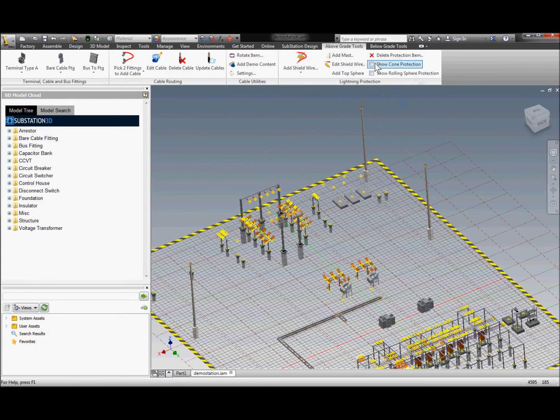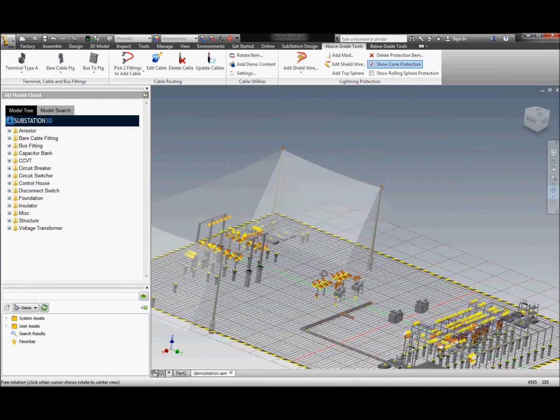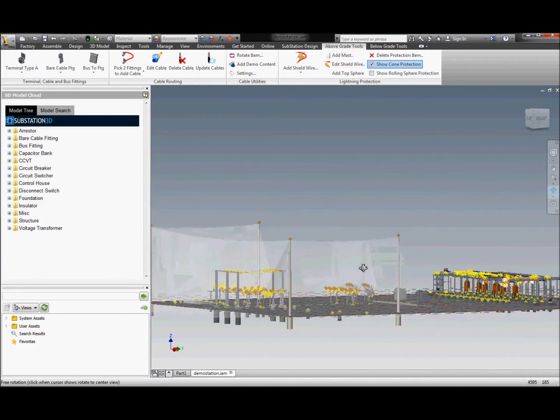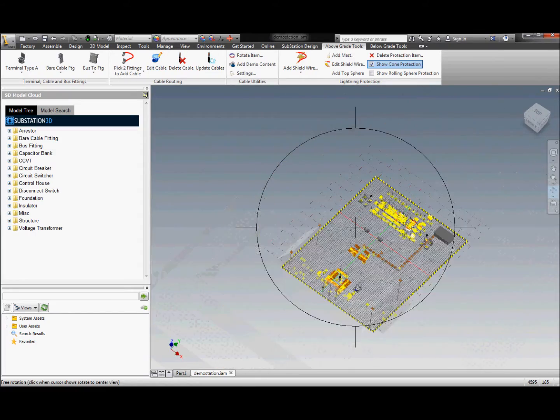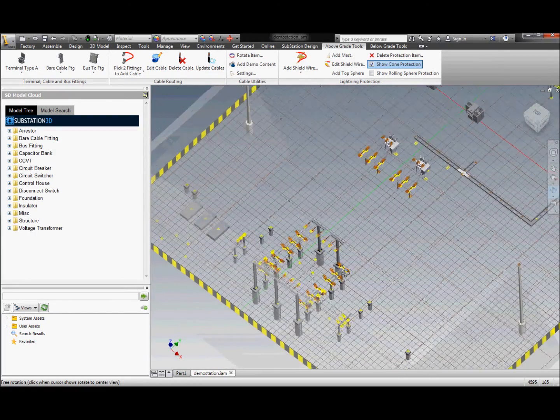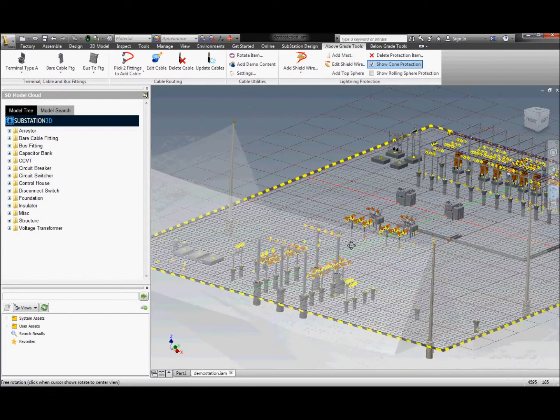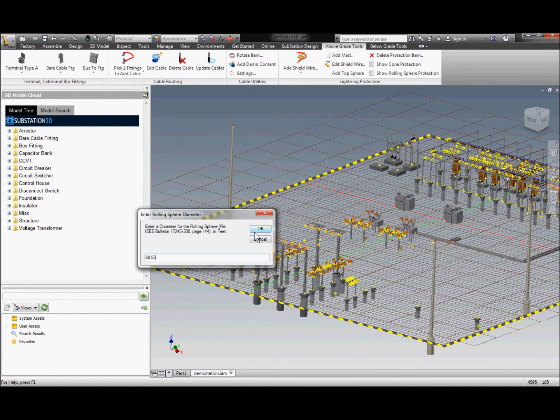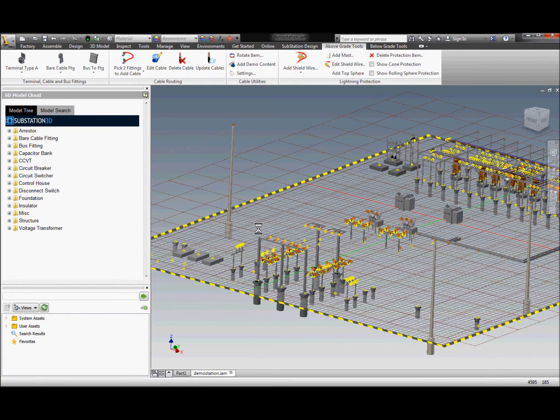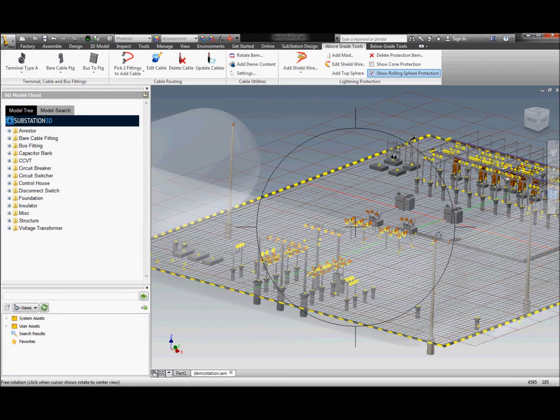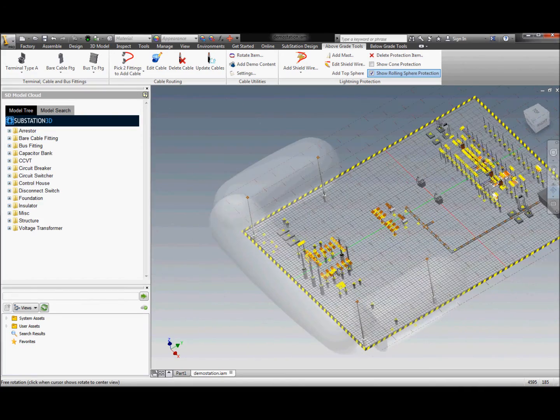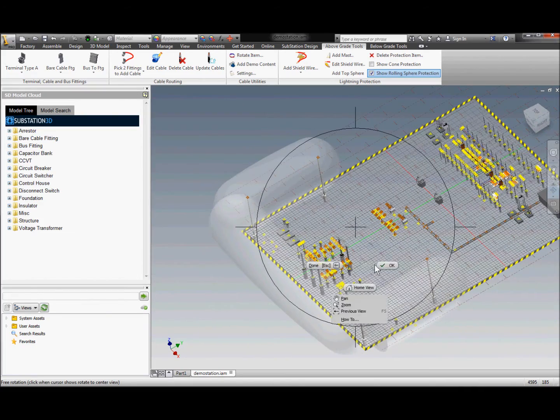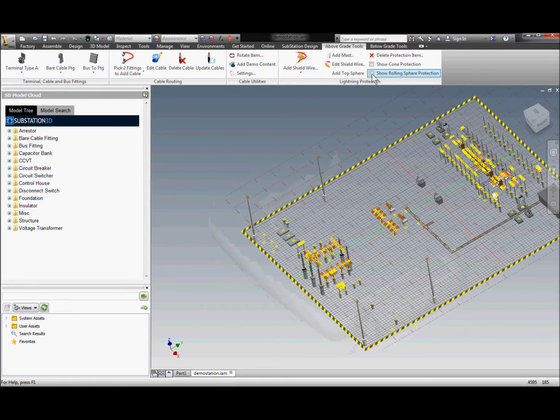With the shield wires in place, we can show cone protection. This creates true Inventor volumes which can be used to do a subtraction of the interfering parts — showing what's inside and outside that envelope — and also gives you a visual representation that you can walk through and move around the model to see if anything's touching. It's both a cone protection type and a rolling sphere method, which is the IEEE method for calculating the rolling sphere along those shield wires.